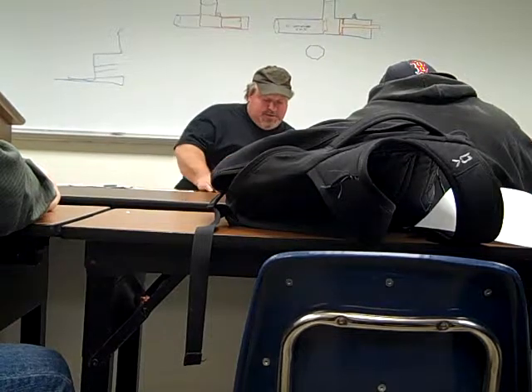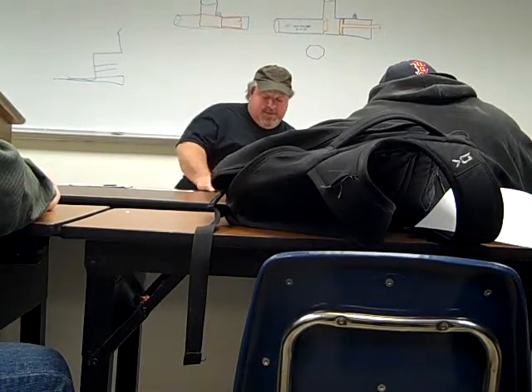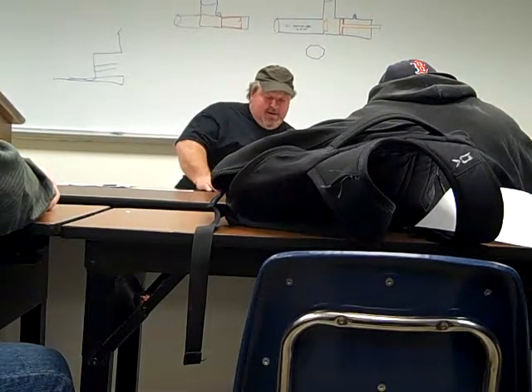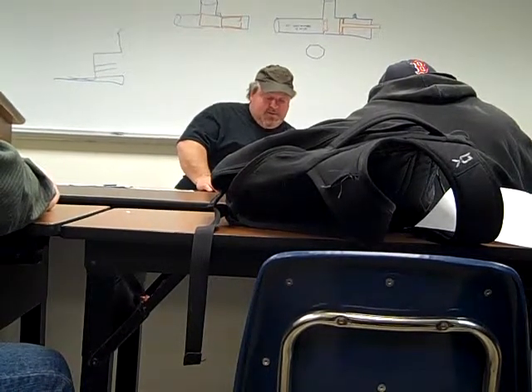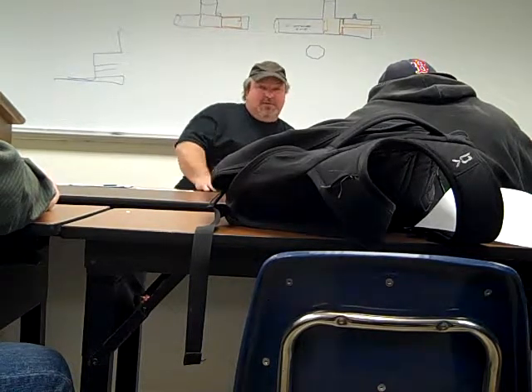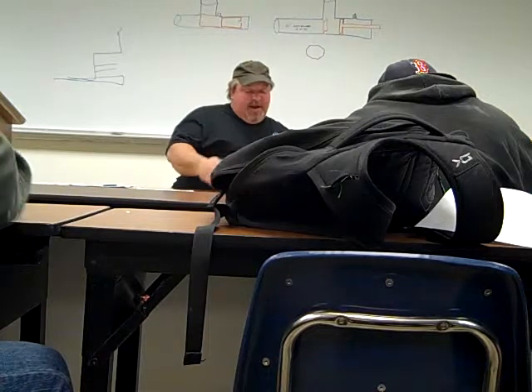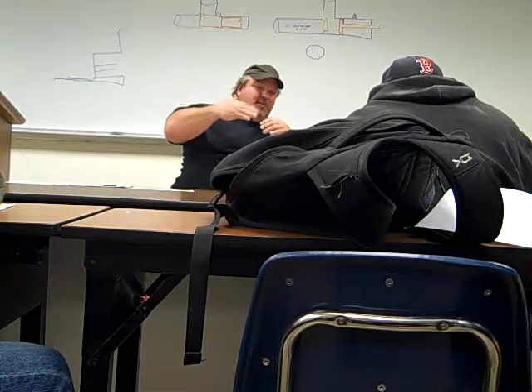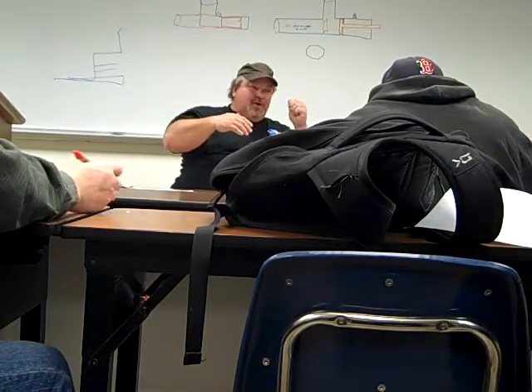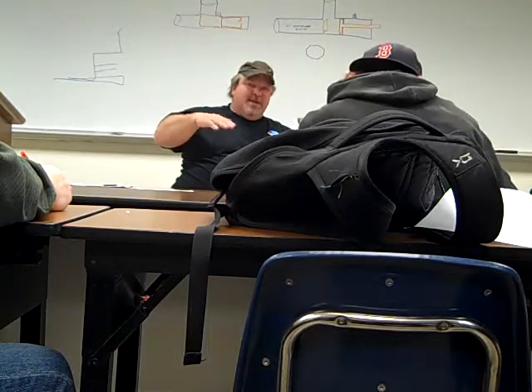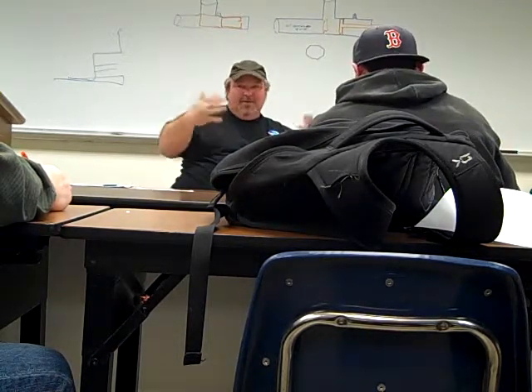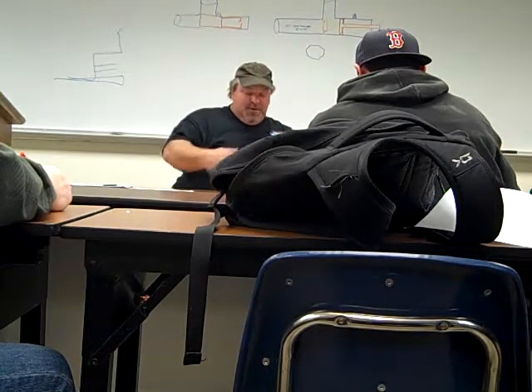He said he's never had that question, but someone's told him that it's been on the test. And it's just 0 and 0. So it doesn't matter, you just gotta pull it down to 0 inches. But you gotta be careful, even though you put your recovery machine onto it and you pull it down, and if you watch it and it gets right to 0, you turn it off, you can't just automatically start cutting lines, because there's still residual refrigerant in there. You really should let it pull down to the 10 inches below and let itself shut off, and then let it build the pressure back up, come back on, to where you know that you're good at 0, there's no refrigerant left in it.